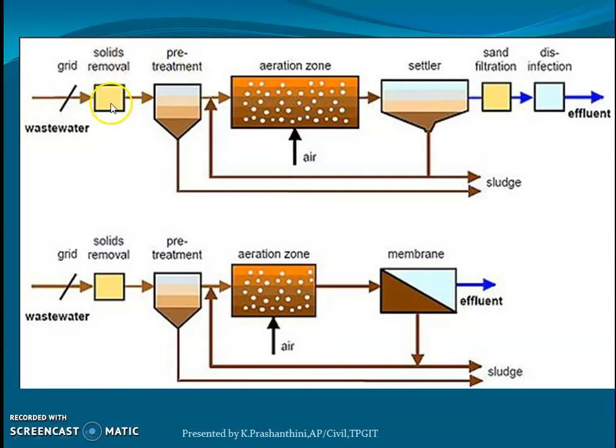The effluent from the solid removal enters the pre-treatment unit, which consists of a primary sedimentation tank, followed by an aeration zone and a secondary sedimentation tank, and then a sand filter for further removal of suspended solids, before being disinfected and discharged.